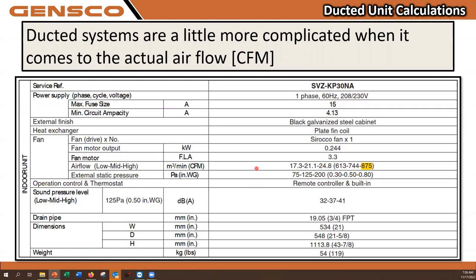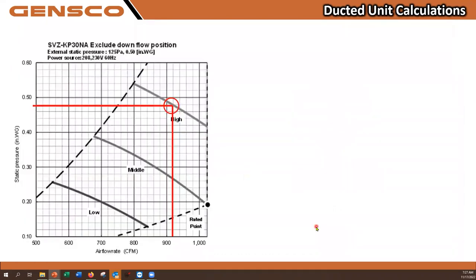It has a high-speed fan rating where it's rated at 875 CFM. If I go to the service manual and look at the blower chart, the actual CFM output can depend on the actual static pressure. So from the factory, this unit came with a set point of 0.5 inches of static pressure. If I measure my static and it's actually 0.48, and I've made a line on the blower chart, anything within these dashed lines is valid numbers. Anything outside of those dashed lines are maybe, maybe not.